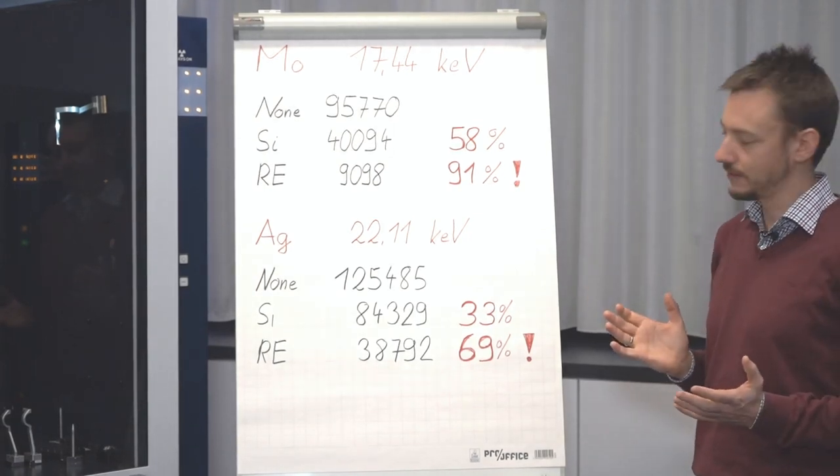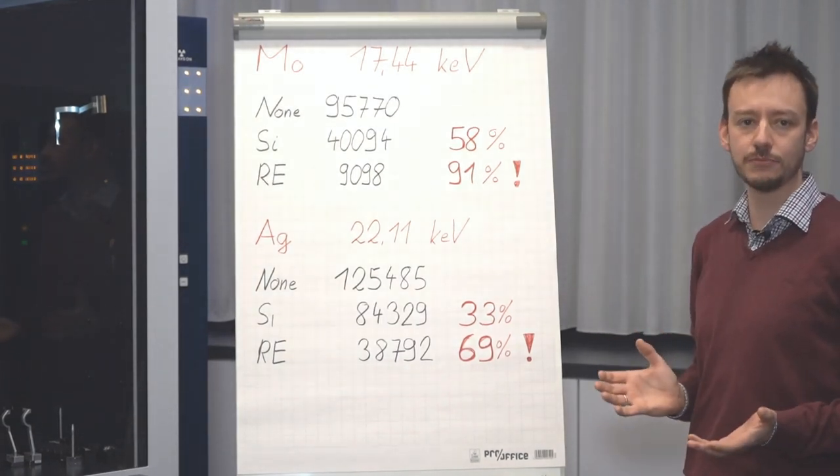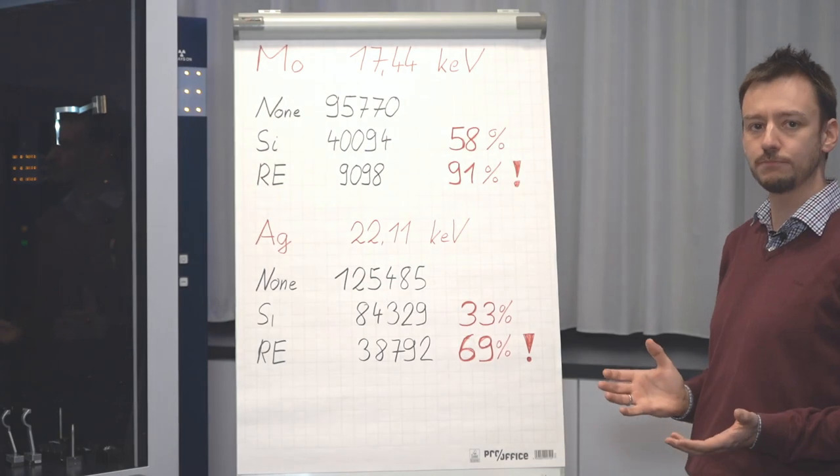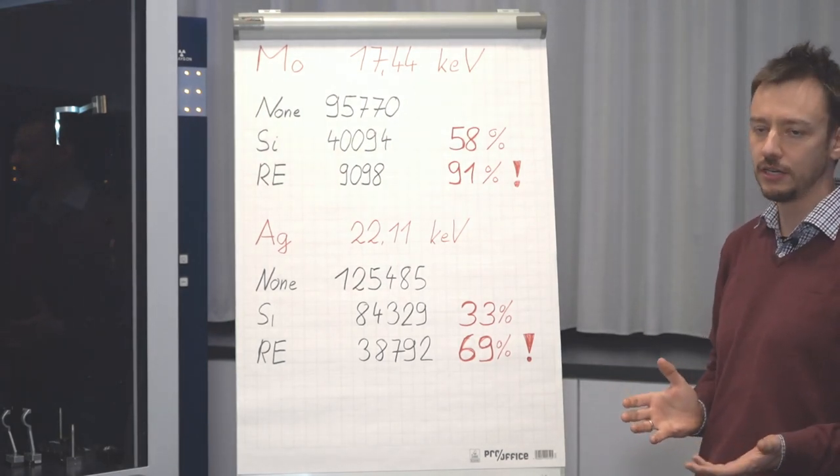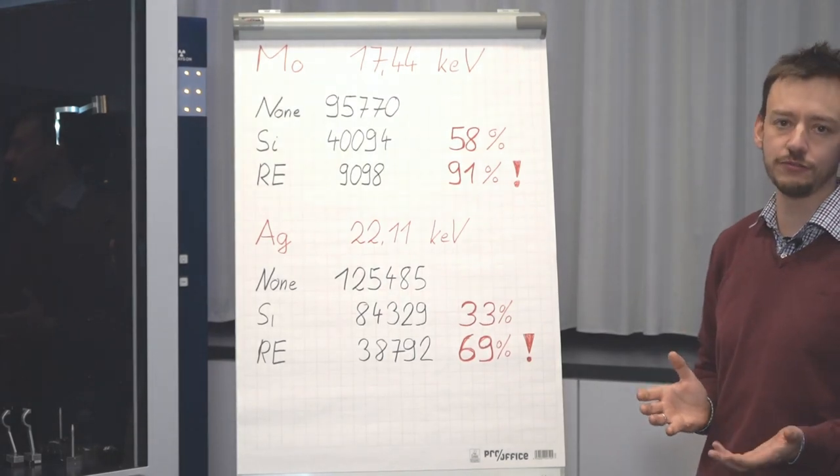So to summarize this silicon is just not a good absorber for hard radiation. If you want to properly detect harder radiation like molybdenum or silver you have to go for an x-ray conversion material.